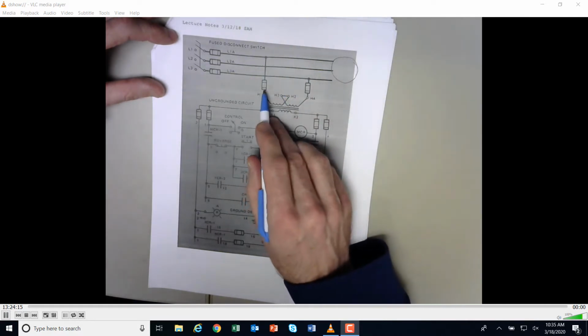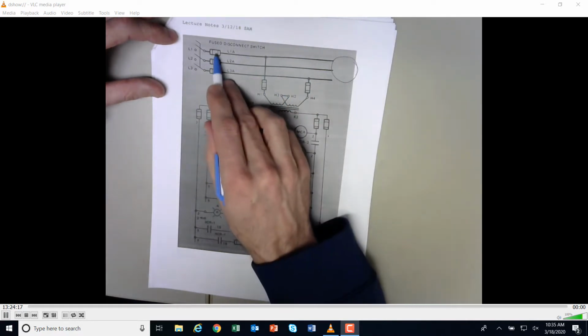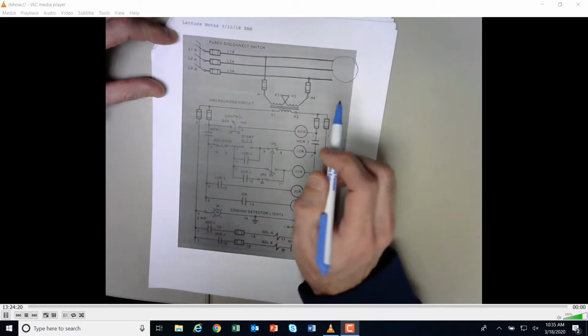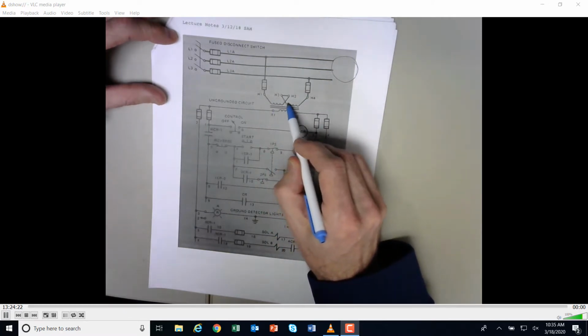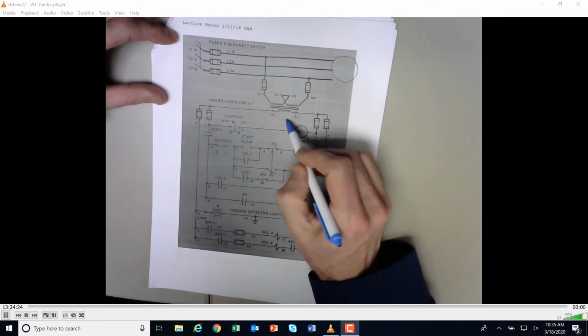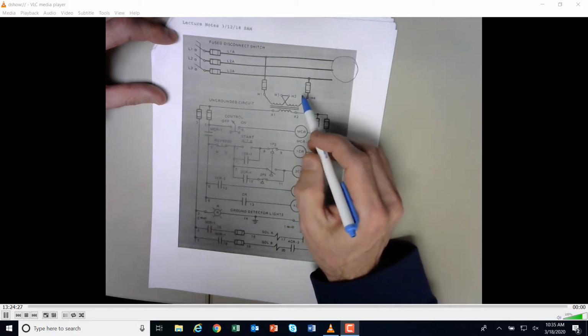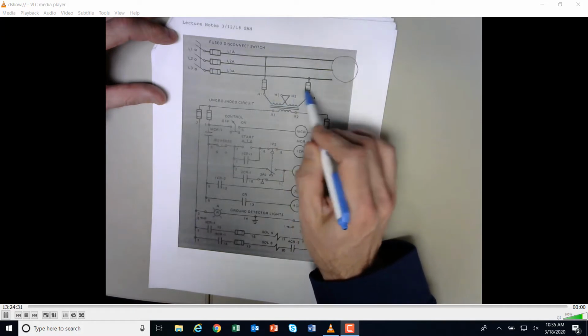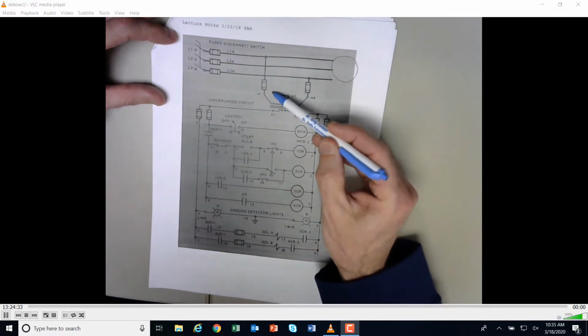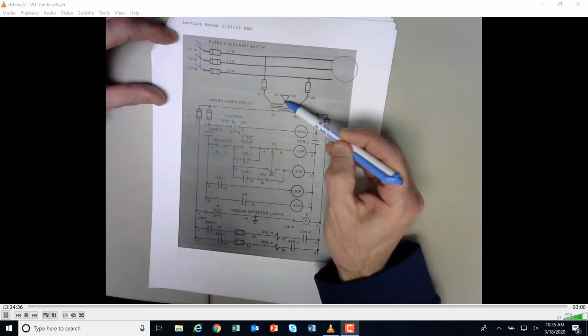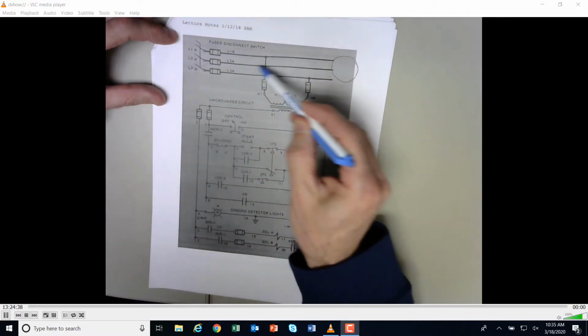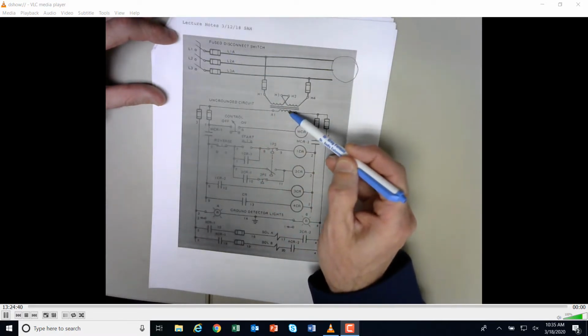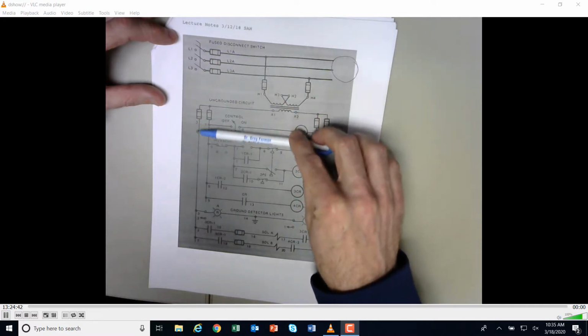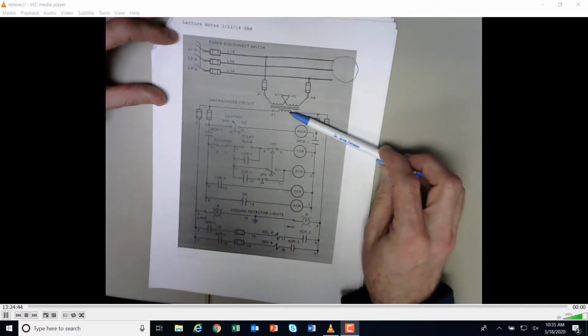Now, there's the next fuses here. Let's say these are good. These are fused in the transformer. So for some reason this side of the transformer shorts, or we're drawing too much voltage, or too much current in one of these, and one pops, well then it's going to bring down the transformer. It's going to leave the power circuit intact, but that means that if the transformer goes down, then everything here is going to die because the secondary is going to come down. So that's a second level of fusing.